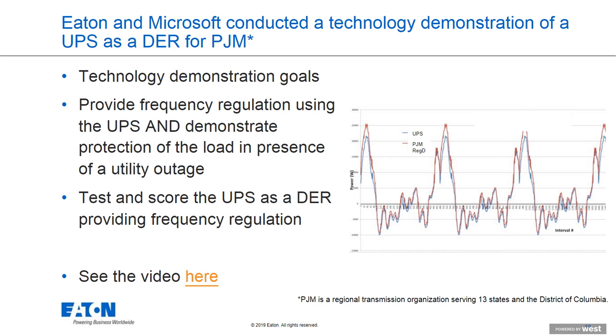What's the test? On the right-hand side of this slide, you see the red waveform, a signal from PJM saying this is what we need you to track. If we're overly high on the red waveform, we need the UPS—the blue waveform—to be a bit below it and absorb some of that extra demand. When we go below the center line, we need the blue line to be a bit larger amplitude than the red line and supply energy to the grid. The same pattern repeats over and over.